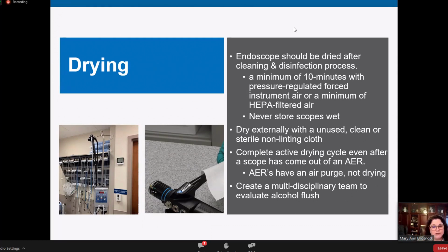They don't have drying cycles. They have air purge cycles. Those scopes are still wet. Yes, even if you've done an alcohol flush on them. Yes, even if it's going into a regular storage cabinet. Or it can go into a drying cabinet, and a drying cabinet is one hooked up with active air lines directly to the channels that either continually blow air through those channels to dry or have a validated cycle to achieve drying. So again, every scope, every time, completely dried.